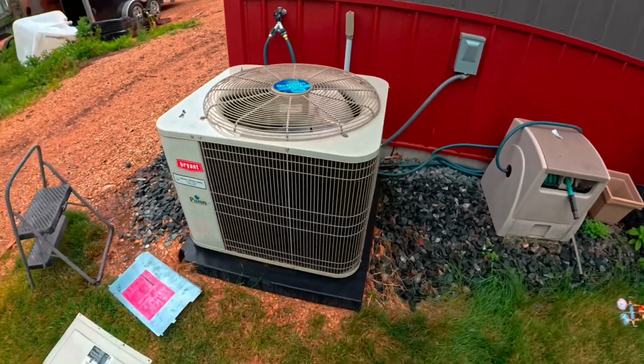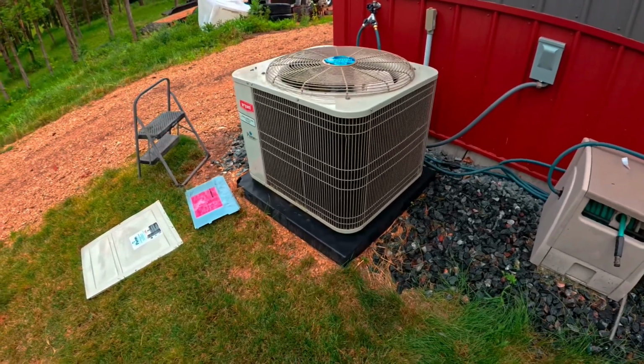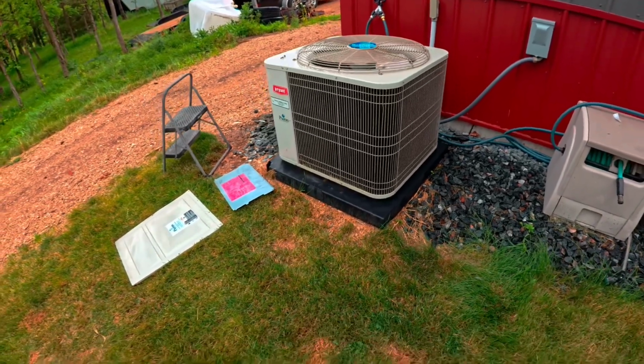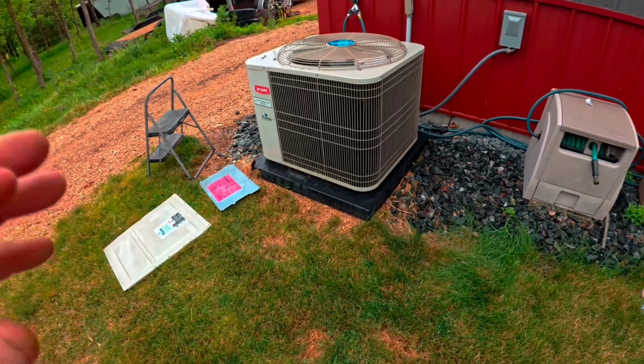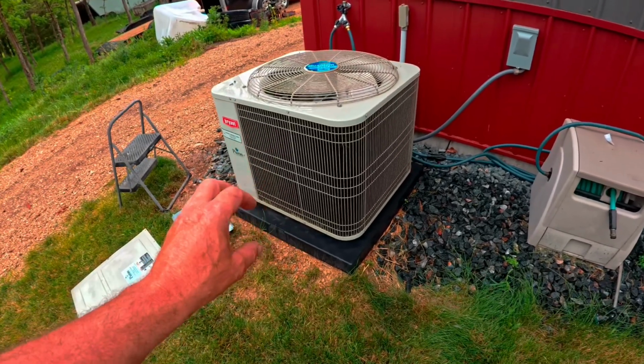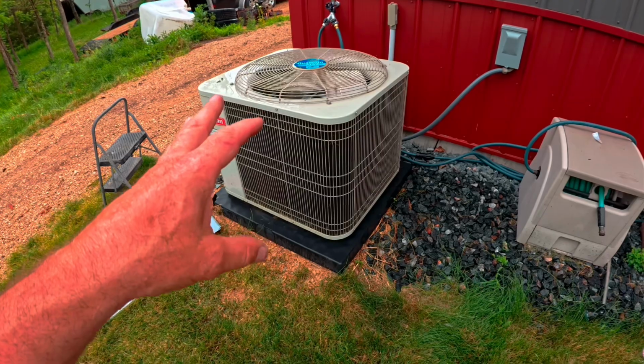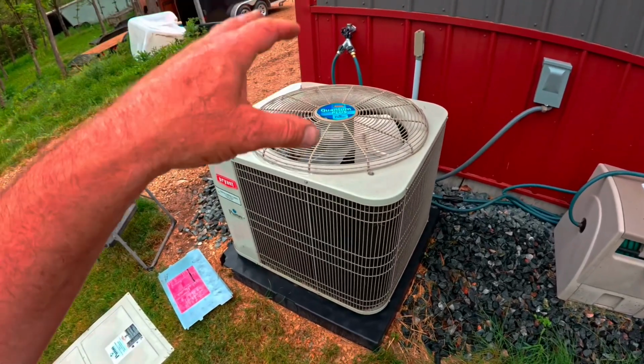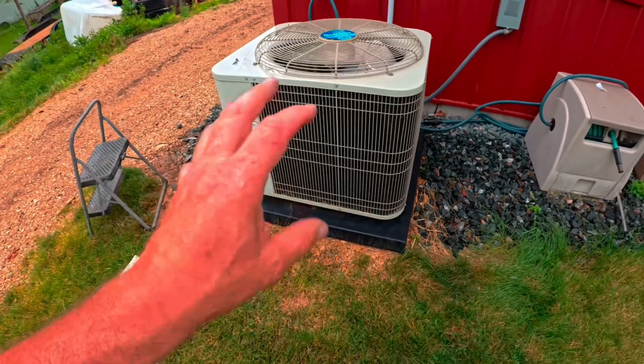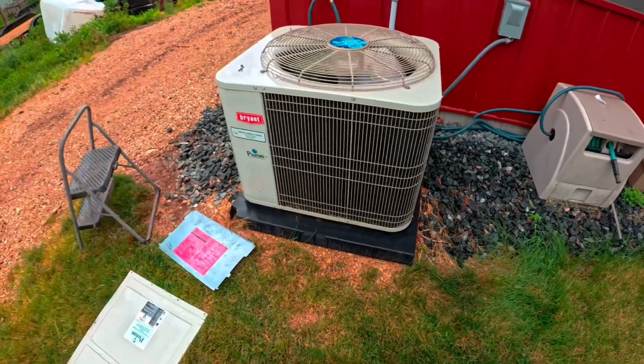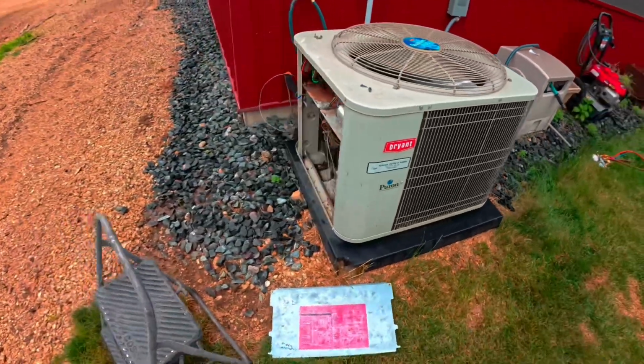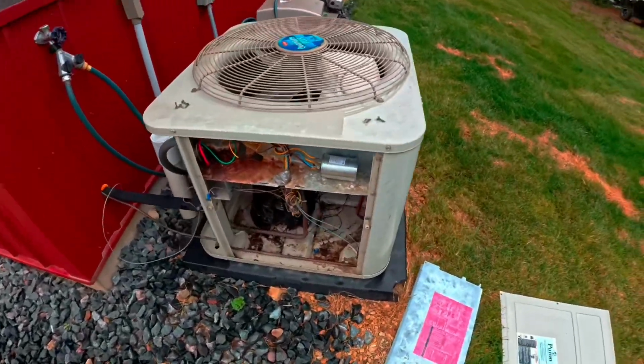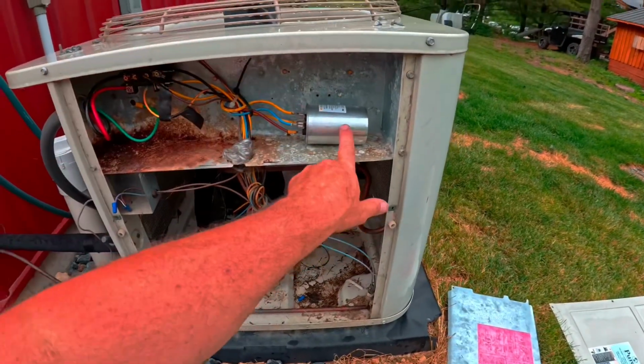All right, everybody. Third and final scenario. You come home, the house is warm, the indoor fan is running, so you come out here to check the outdoor unit, and it's trying to run, which means the fan is trying to start, or the compressor is trying to start, but it can't. If you run into that situation, 9 times out of 10, you're going to be dealing with the capacitor.